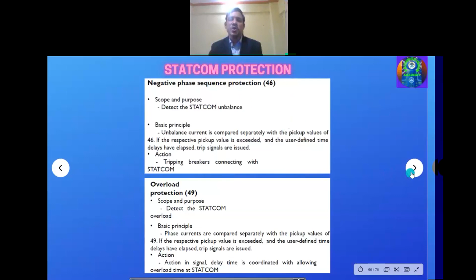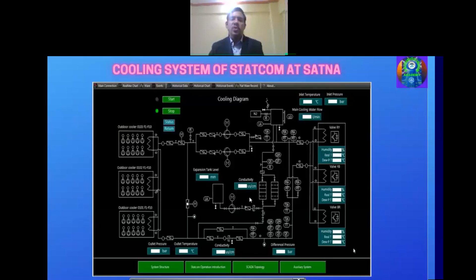So this is the cooling system of the STATCOM. It's the most important system for the successful operation of the STATCOM. If the cooling system is not maintained, you cannot perform any action by the STATCOM. In this cooling system, we have to maintain the conductivity of the water. We have to use DM water, demineralized water, and the conductivity should be monitored. It should be very low, sometimes 0.8 microsiemens per centimeter like this. So that much we have to maintain. If the conductivity increases, then there will be a short circuit of the IGBT modules. Also, you have to maintain the flow of this DM water. If the flow rate changes, then there will be tripping of the STATCOM. So there are so many protections given for this STATCOM.